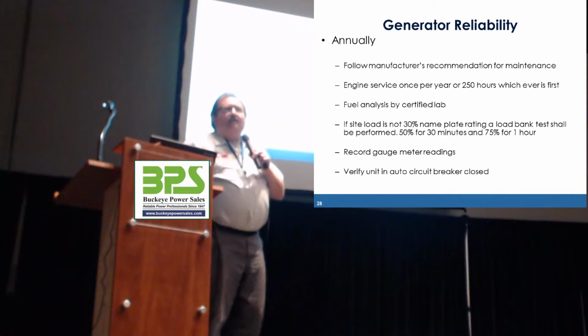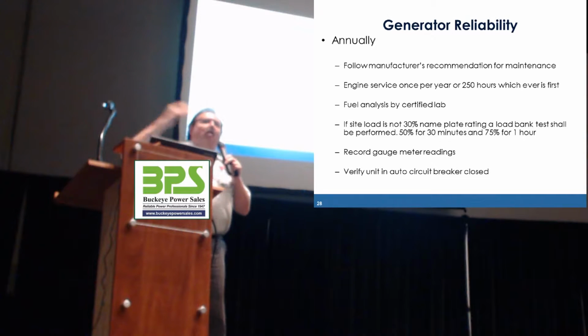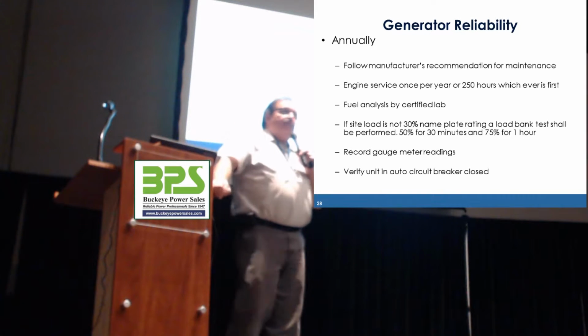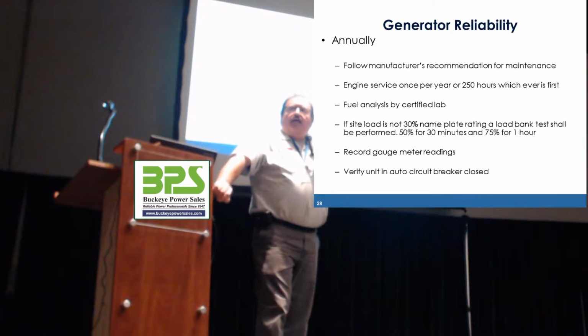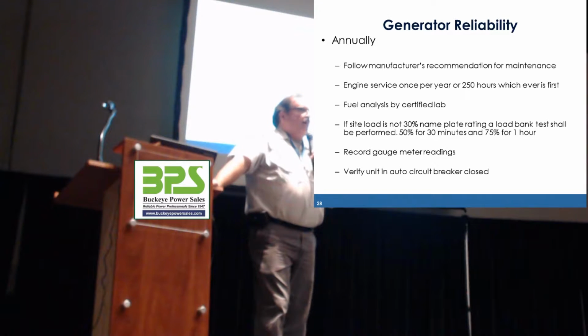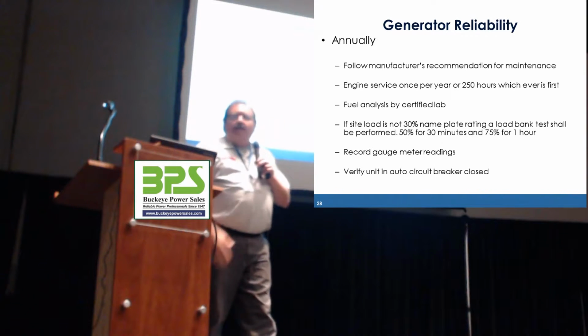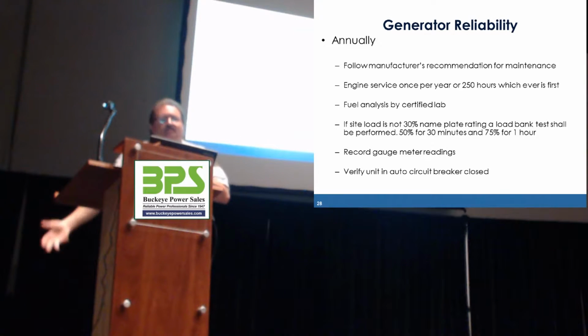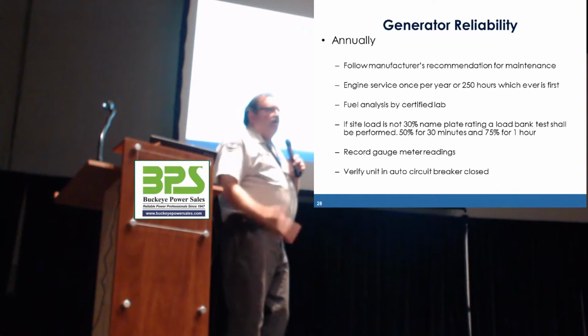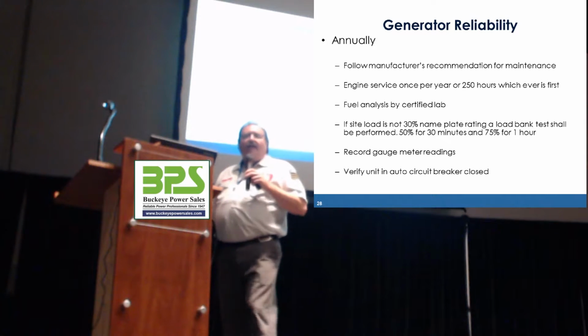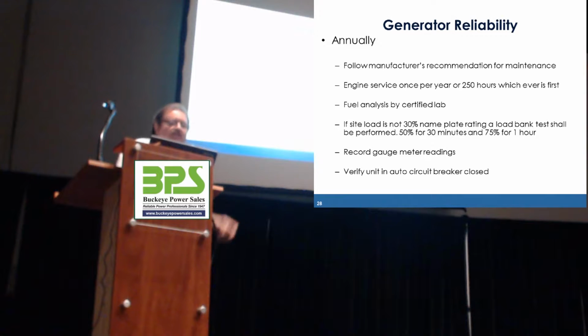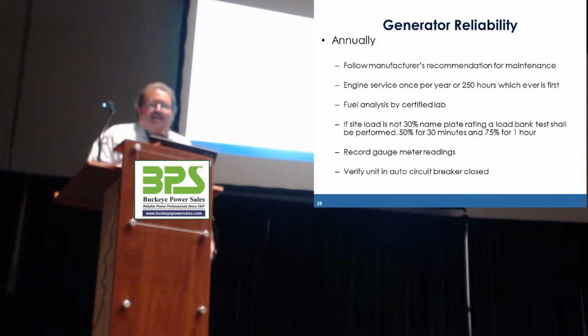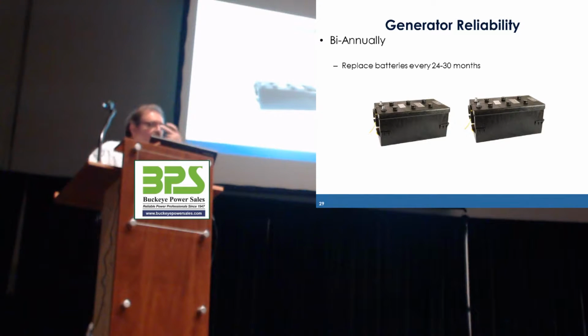Also, you would rather have a failure when you're testing it than when you're 18 hours into a 24-hour power outage. So when you're putting it under load, you want to think of it like taking a stress test or putting a car on a dyno. Any weakness that machine has is going to become evident during that load bank testing. And again, we're going to record it, document it, and make sure everything's back in automatic when we're ready to go.